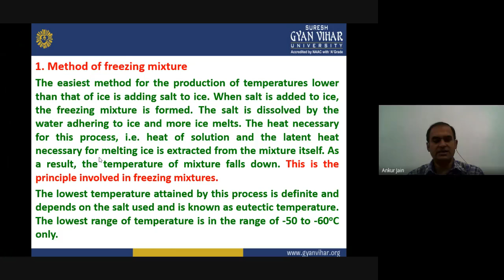But there is a limitation of this method. The lowest temperature achieved by this process was not very low. It depends directly on which salt we are using, and that is known as the eutectic temperature. The lowest temperature which we can achieve from this method lies in the range of minus 50 to minus 60 degrees centigrade. For example, if we use different salts such as magnesium chloride, NH4Cl or NaNO3, we can achieve different temperatures ranging from minus 4 degrees to minus 55 or minus 60 degrees centigrade. The lowest possible temperature known until now is by using calcium chloride, at minus 55 degrees centigrade.